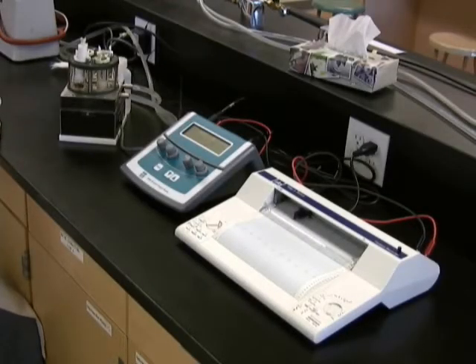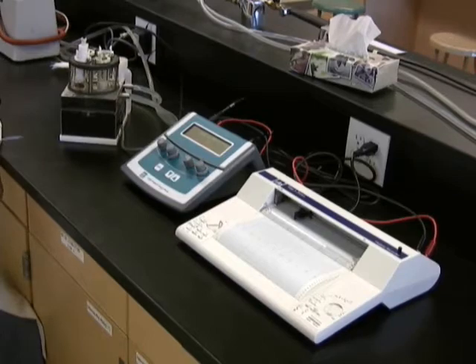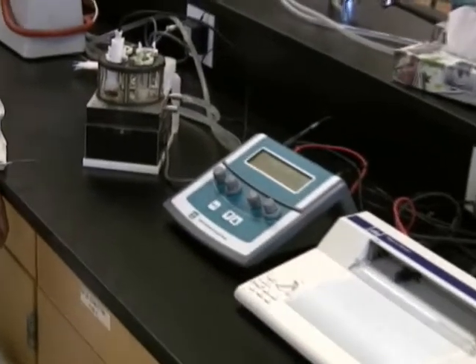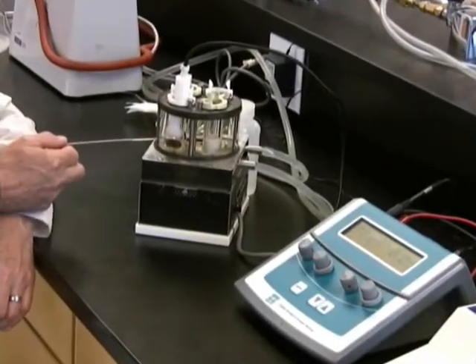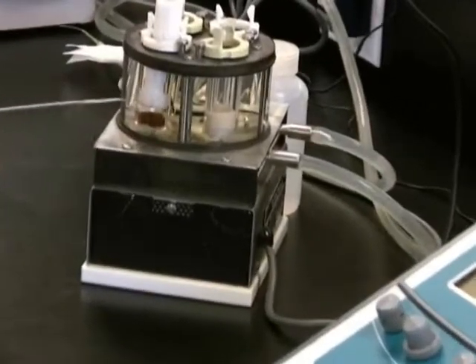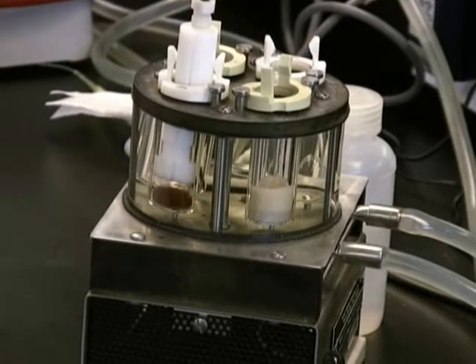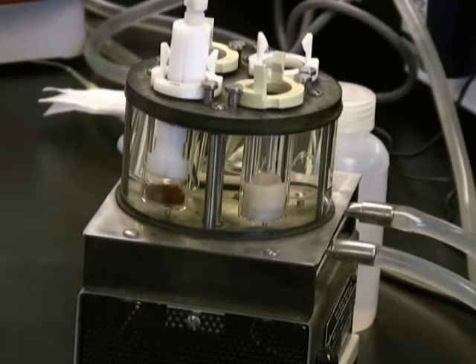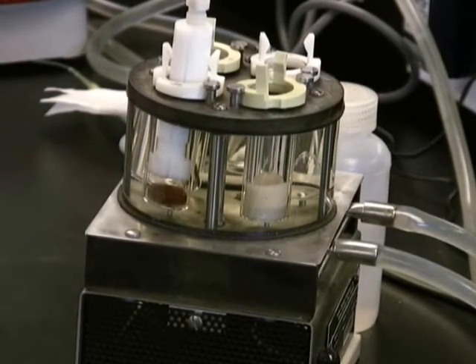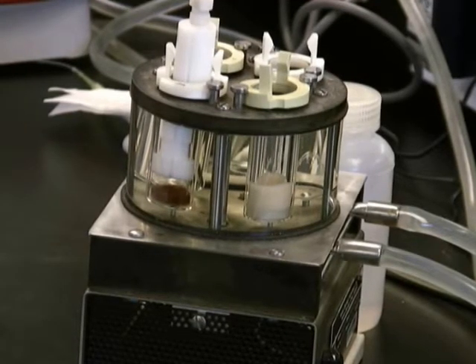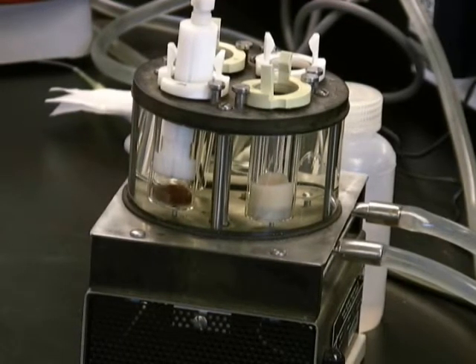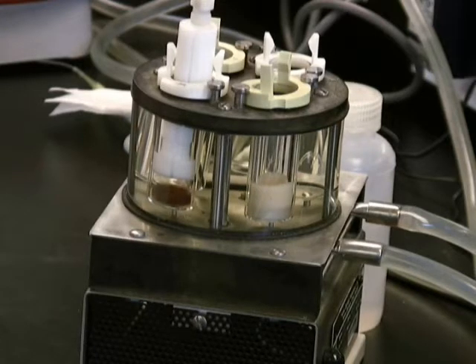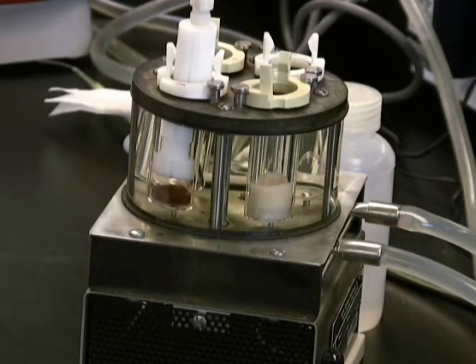So now we're ready to do calibration. One thing before we finalize the calibration, we need to understand what's happening within the cell. We have to remember when we prepared the electrode, we added an electrolyte to join the platinum to the silver, and we put a membrane. This membrane is permeable to all gases, but within the membrane only oxygen is disappearing. So when the system is plugged in, within about half a second, we are very low in oxygen within the electrolyte.